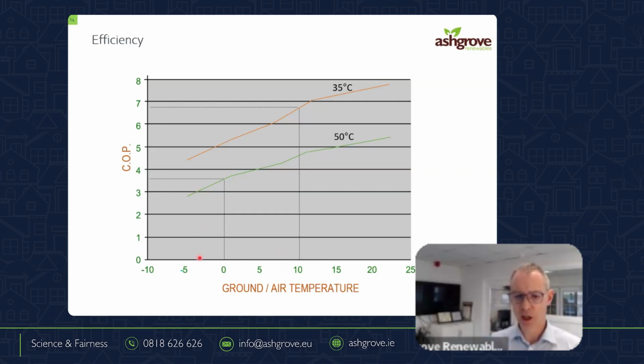If I do that at the same time as I've designed the underfloor heating, the heating system wrong, so my radiators are too small, my distribution pipework is too small or whatever, and I need to run now at 50 degrees. So you can see I could be down here in one scenario at a COP of 3. If my ground collector is big enough, we'll say 10, and I'm running underfloor heating at 35, I'm up at 7. So I've halved my running costs just by good design. Same heat pump, but I've halved literally my running costs.